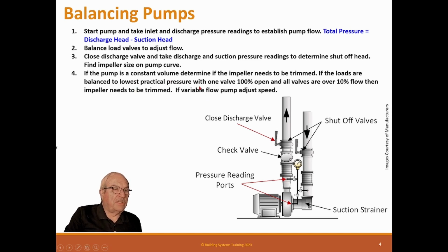Okay, if the pump is constant volume, determine if the impeller needs to be trimmed. If the loads are balanced to the lowest practical pressure with one valve 100% open, and all valves are over 10% flow, then the impeller needs to be trimmed. If variable flow, just simply adjust the speed, right? If variable flow, it's no problem.